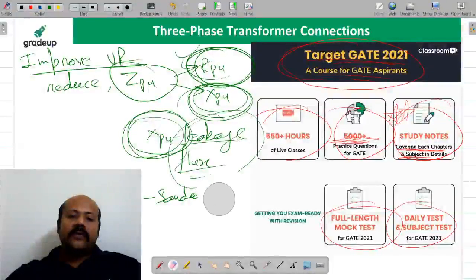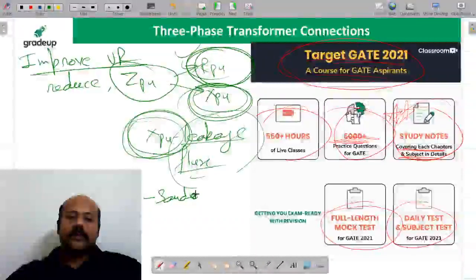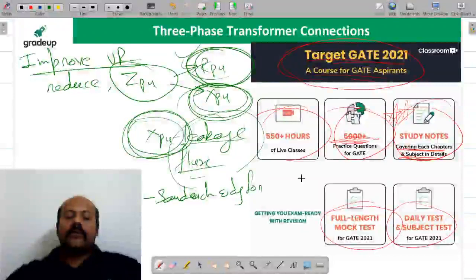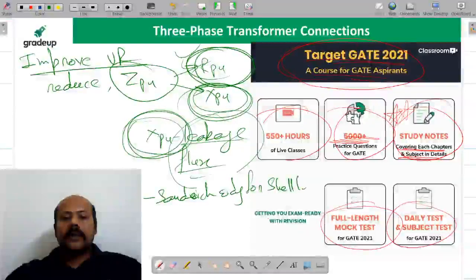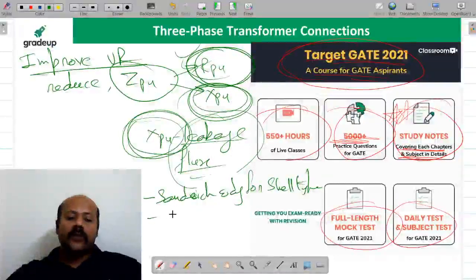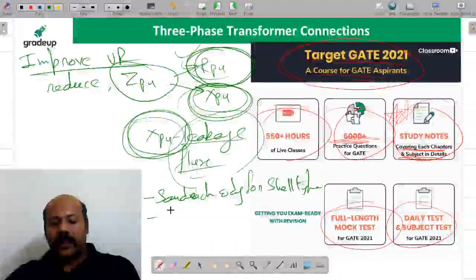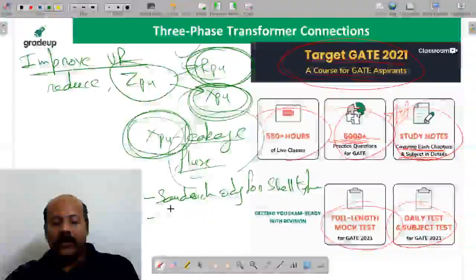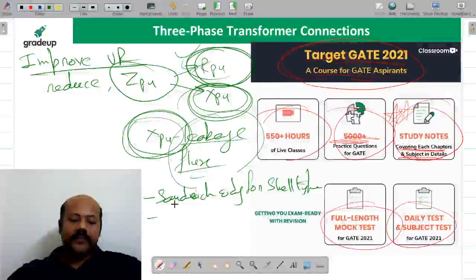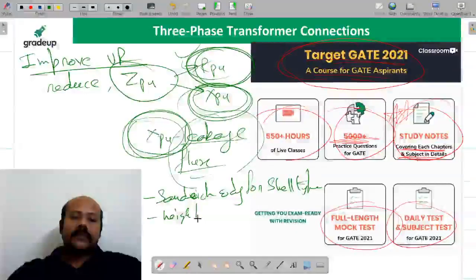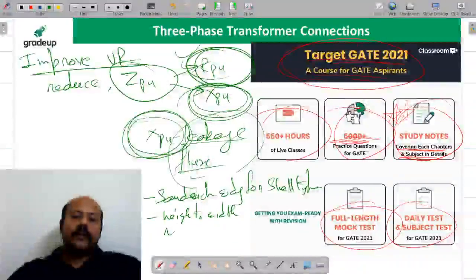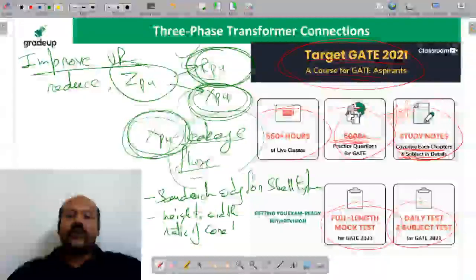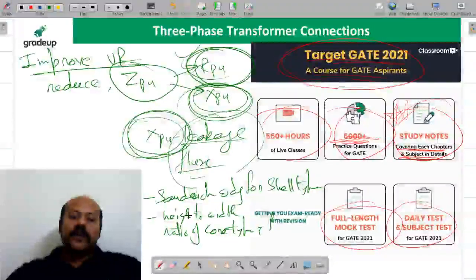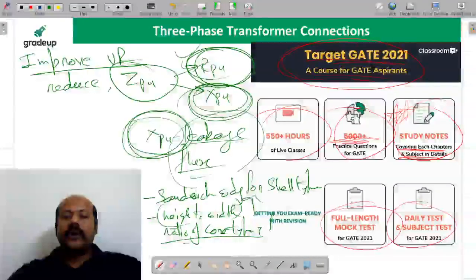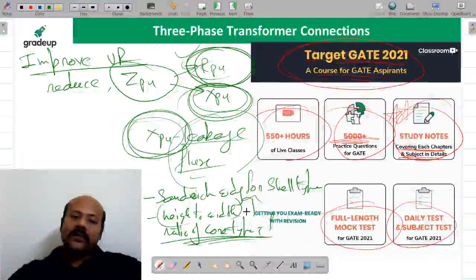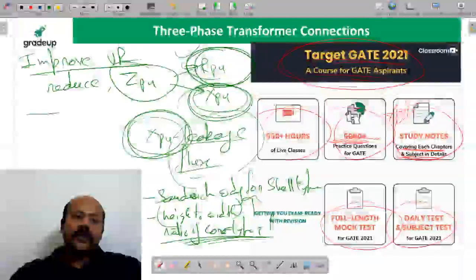You are going to use sandwich windings for shell type transformers, and you are going to have the height to width ratio of the core type transformer increased. If you increase the height to width ratio for the core type transformer, the leakage flux is going to be less, because of this kind of construction.